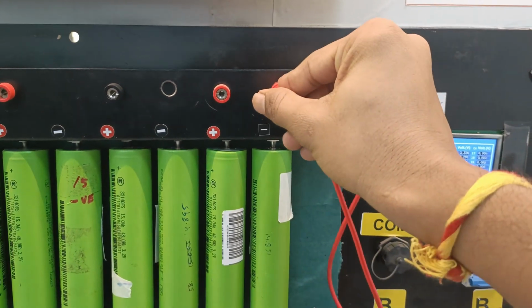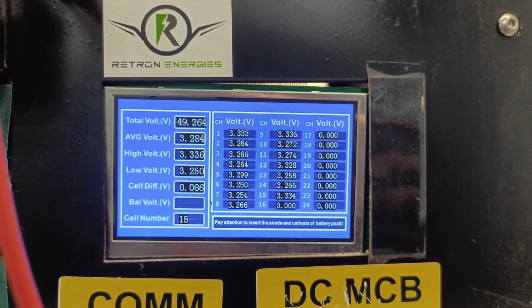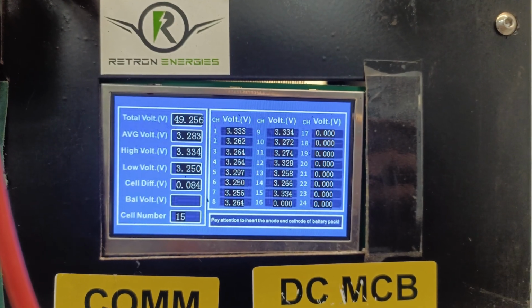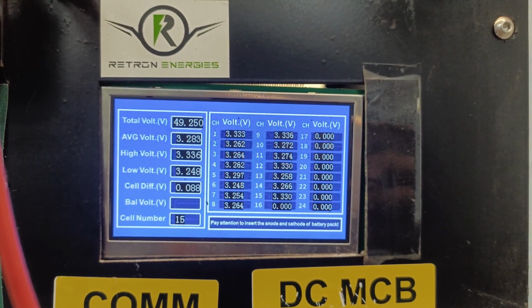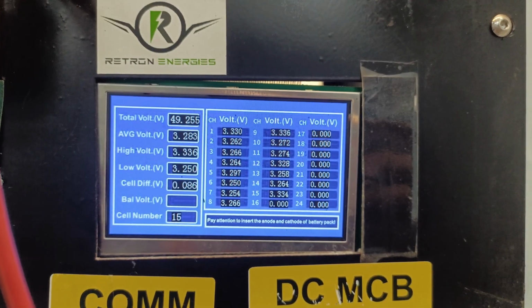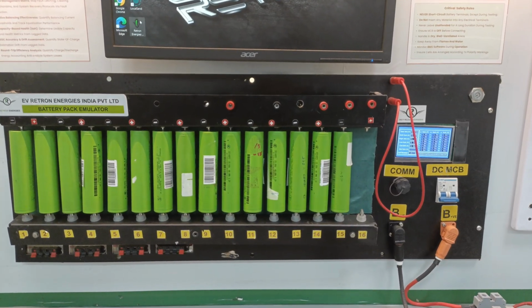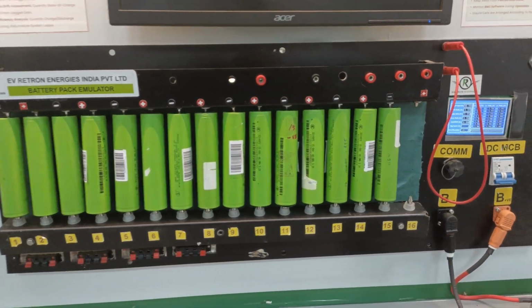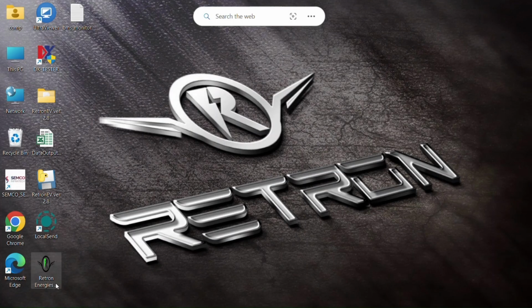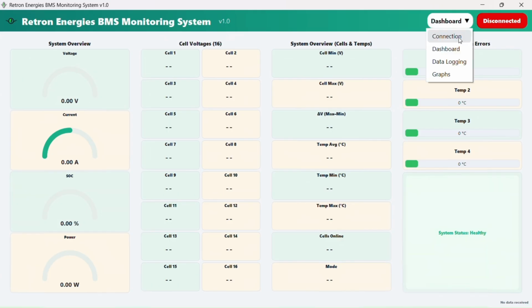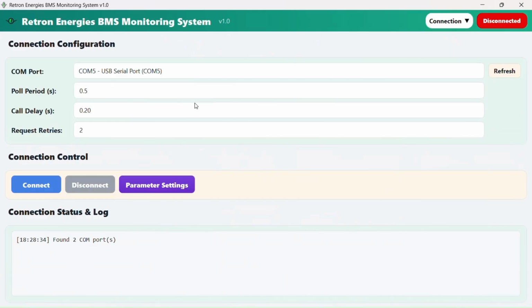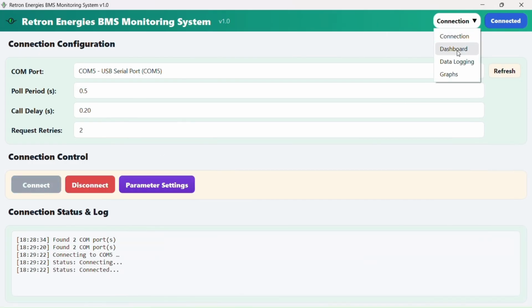The display will start showing battery information in real time. Here we can observe the individual cell voltages, minimum cell voltage, maximum cell voltage, and the total pack voltage. This allows us to verify that all 15 cells are detected correctly and functioning properly. Next, move to the computer and open the BMS application. After launching the software, click on the connection option and select the appropriate communication port. Once the correct port is selected, click Connect to establish communication between the BMS and the application.